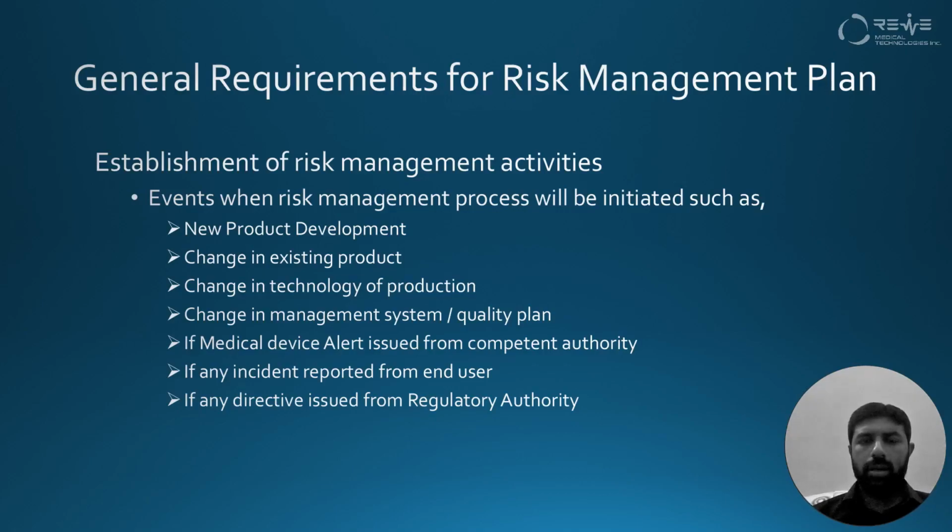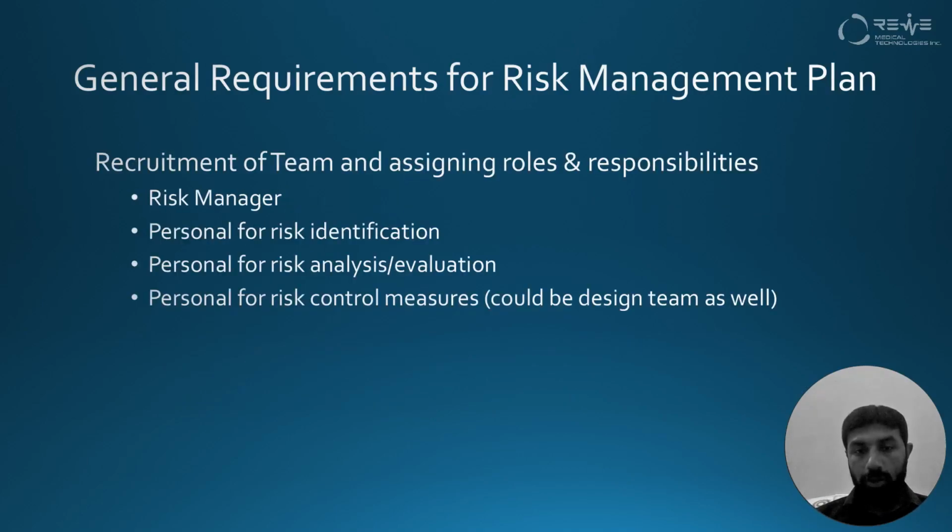Some of the general scenarios are when there is new product development or change in some existing product, or there is change in the technology of production, or change in the management system or the quality plan, or there is some medical device alert from the competent authority, or some incident reported from the end user, or there is some change in the regulation from the regulatory authority.